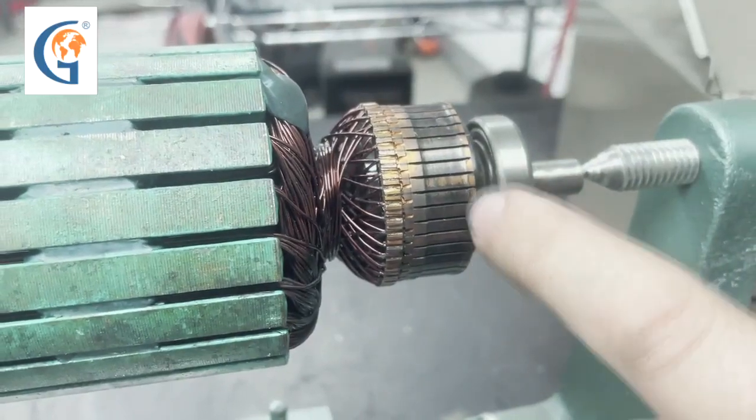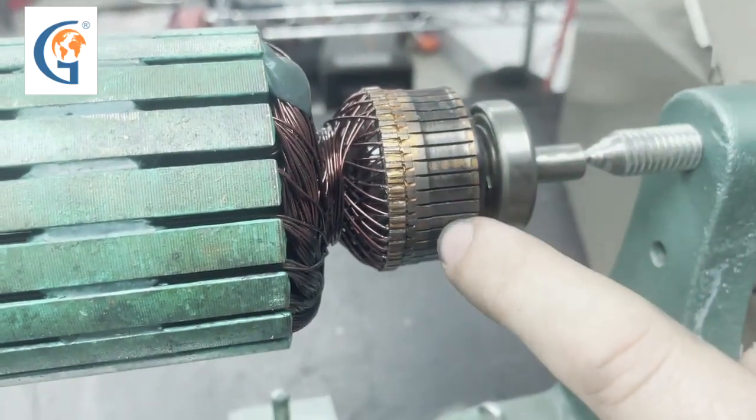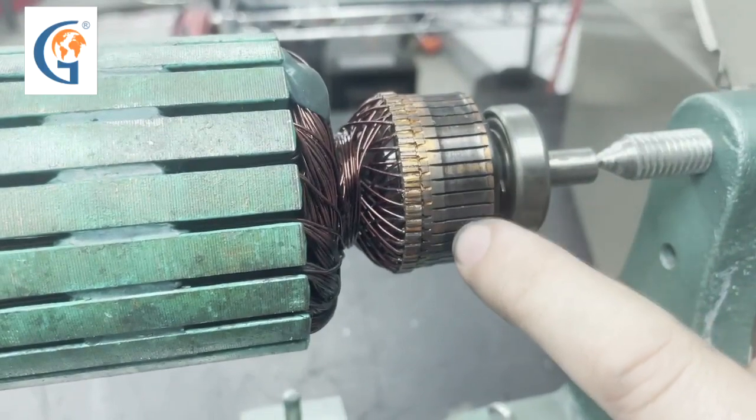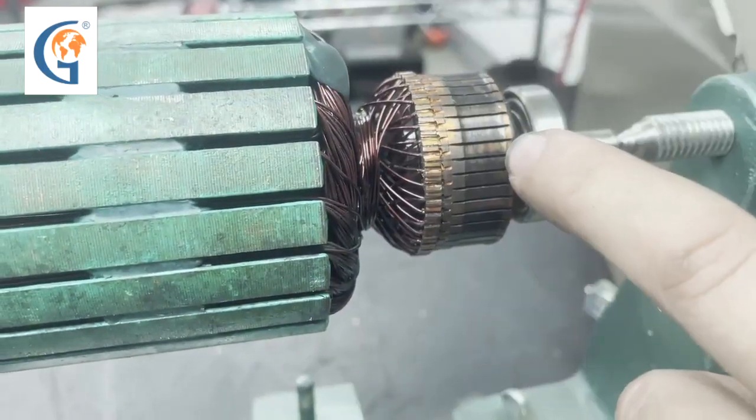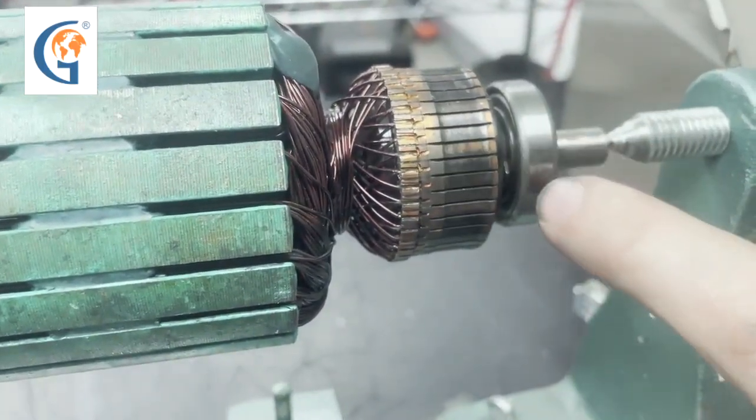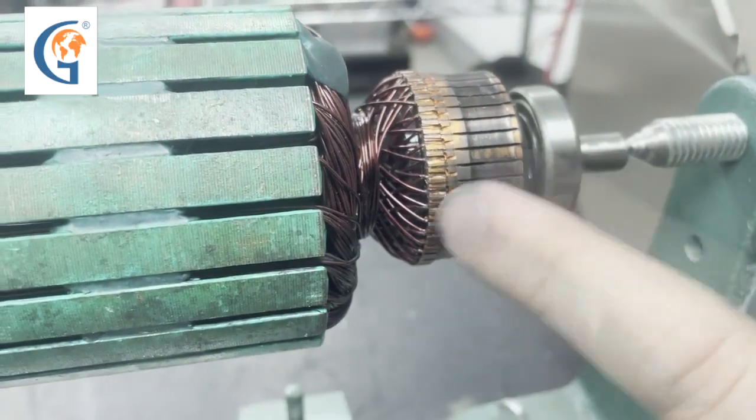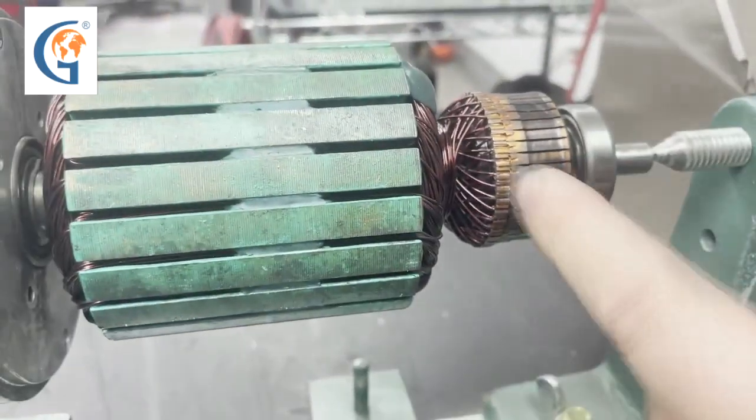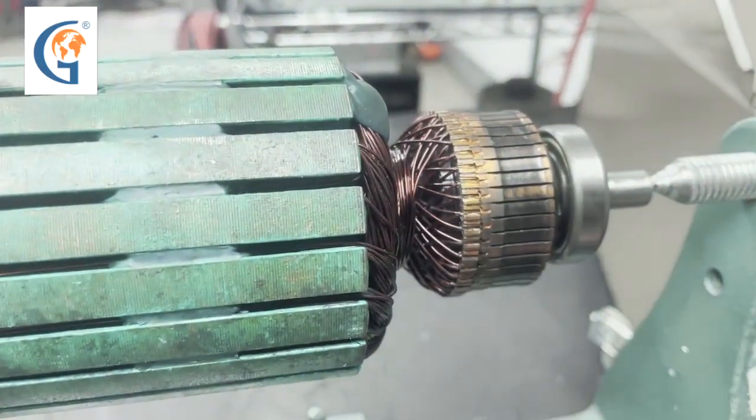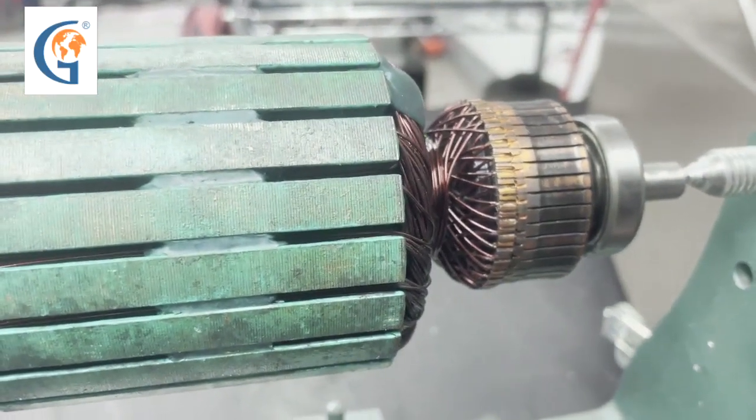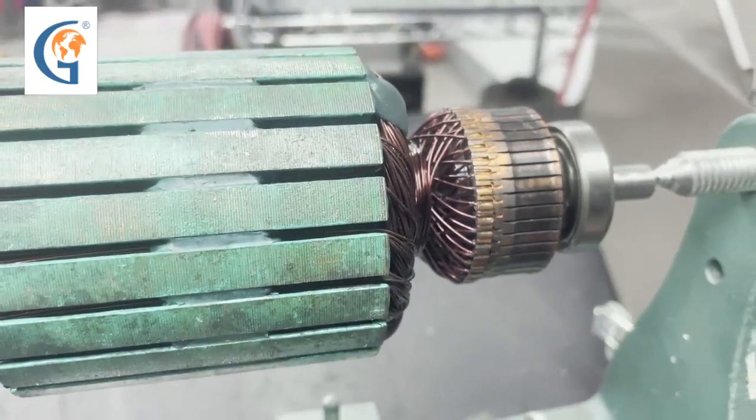The main issue is this commutator has a severe groove in the middle where the brushes have worn down the copper bars over time, which can create problems. You also can see this discoloration and general damage on this commutator. We can also see some darkening within the windings. That might indicate on a visual inspection there is a problem.